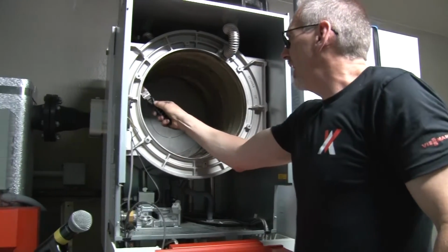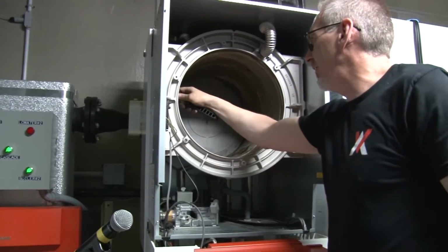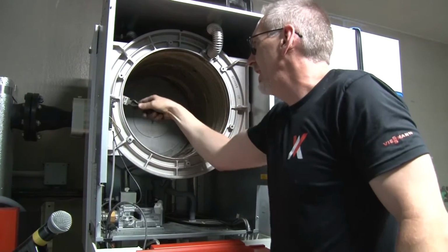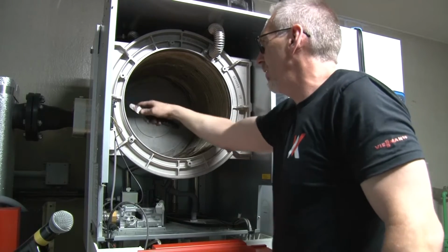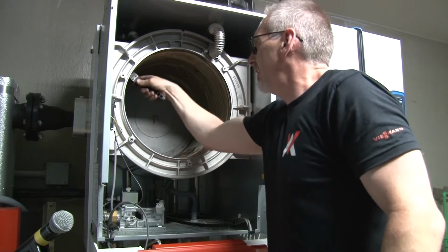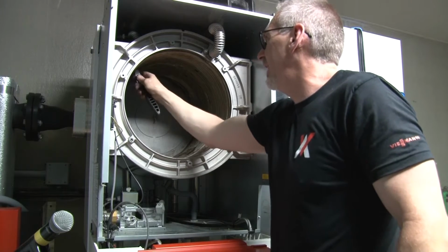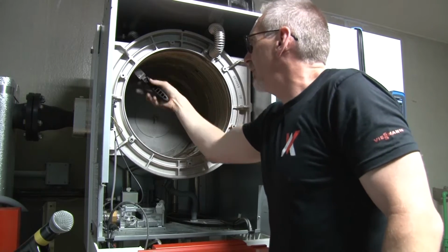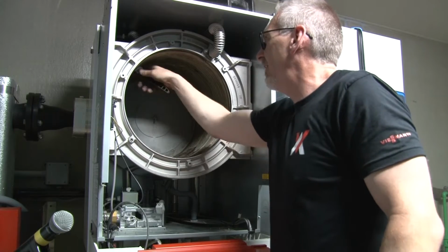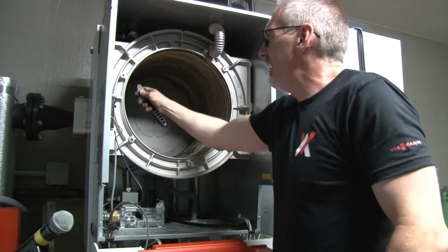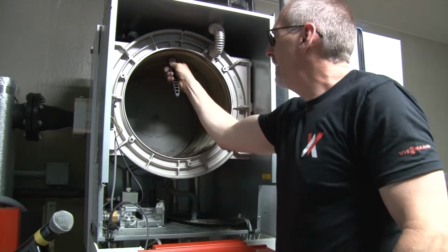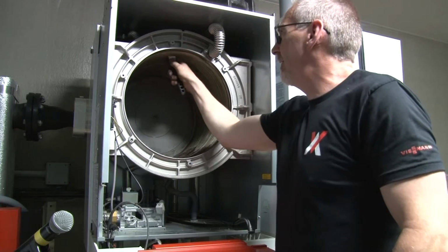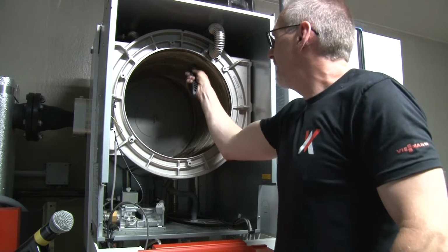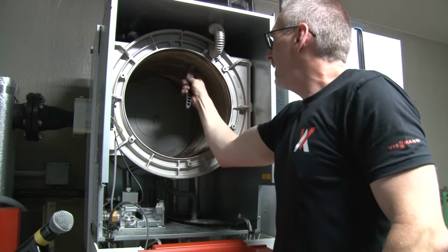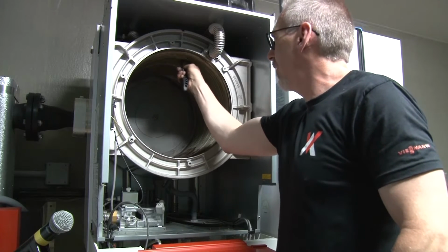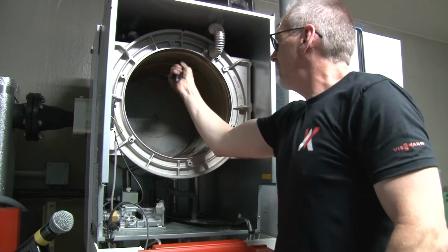And also, if I'm dealing with different issues like F1 faults, vent faults, maybe you have combustion air contamination. I know this blower doesn't have that issue based on the burner, but I'd want to get into these gaps on the top as well, just to make sure that we have no issues. These are nice and clean. But if you have service faults, vent sensor faults in particular, where you have high vent temperatures, you need to go around that whole heat exchanger and make sure all these gaps on the top are nice and open as well, right? To make sure that you don't have any problems. As you can see, this is going through pretty easily on this little heat exchanger here. Just remember that there's some areas I can't go through. There's a dimple there, so I have to move it over a bit and move this little knife through there.